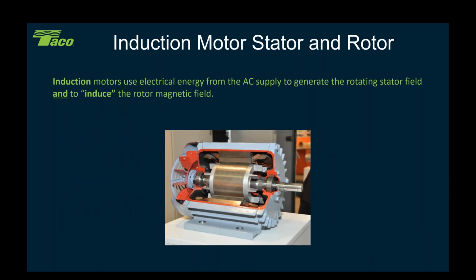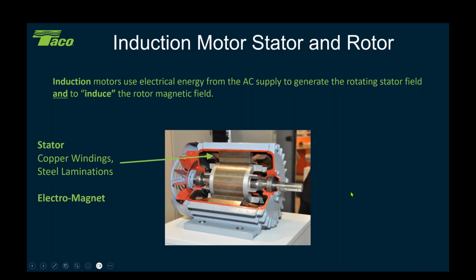Okay, so if we look at a cutaway of what an induction motor looks like, induction motors use the electrical energy from the AC supply to generate the rotational forces and to induce the rotor's magnetic field, because when we apply that electricity to the stator windings, there's three sets of windings in there around the 360 degrees, and that magnetic field rotates in those three windings. And then that induces a current in the rotor and causes the rotor to rotate as well. Out here you can see where the arrow is pointing to, that is the stator, the copper windings and the steel laminations, and that is a giant electromagnet. That's all it is. There's no magic there, I promise, there really isn't.